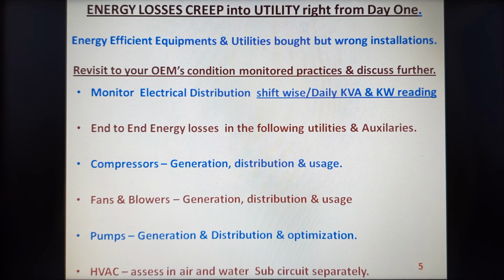First of all, let us try to monitor the electrical distribution either shift wise, day wise, weekly or month wise, both the kVA and kilowatt readings, apart from the basic parameters like volt and amps. This kilowatt and kVA will say whether we are consuming more or less daily. We can definitely see it has a relative impact on our production, and the power consumption can be compared daily.